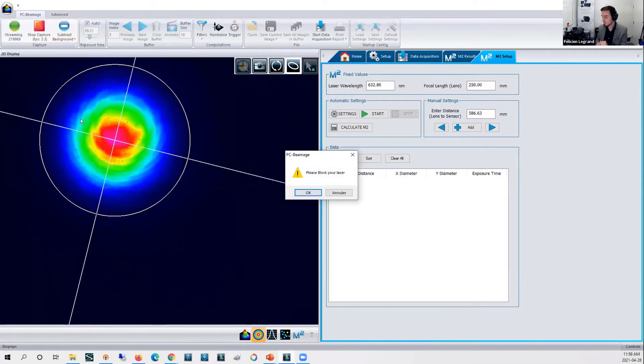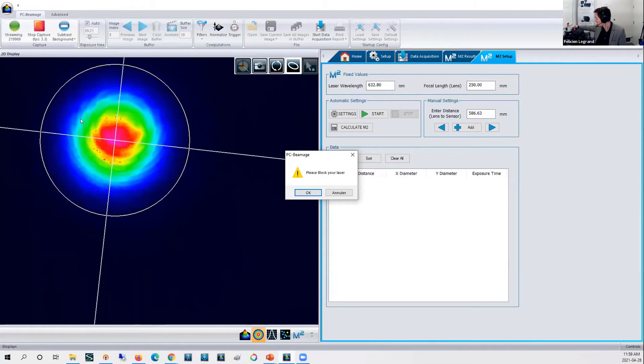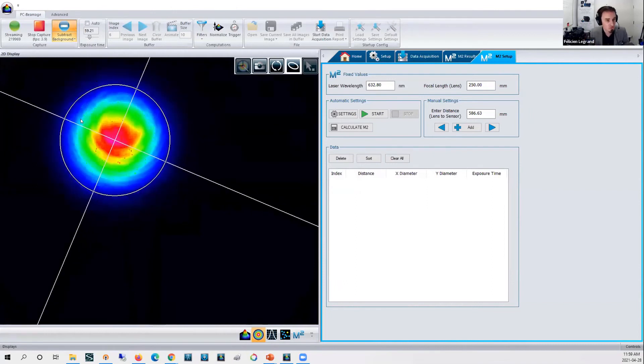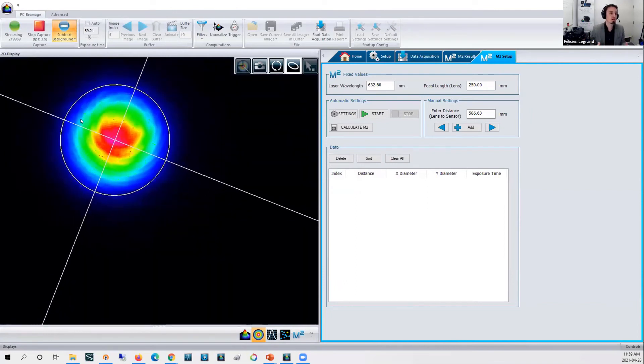It's really simple. Press that button, software will tell me that I need to block my laser beam, which I'm going to do with my card here. Blocking the beam, pressing okay. Software will acquire 10 frames, make an average of those 10 frames, and subtract the average to the actual signal. There you have a nice signal-to-noise ratio as maximum as possible and a good definition of the X and Y axis, which is all automatic.